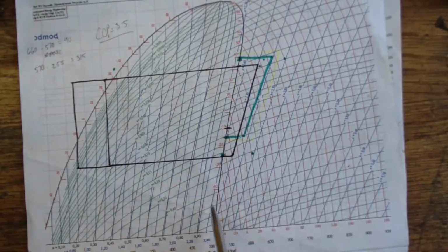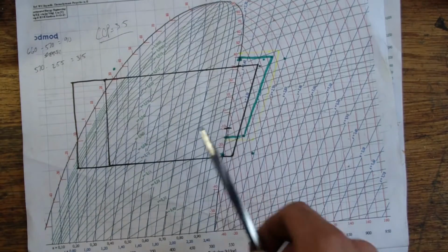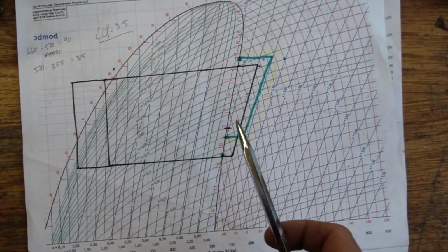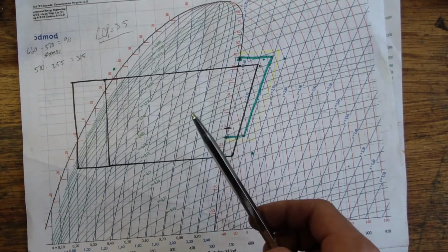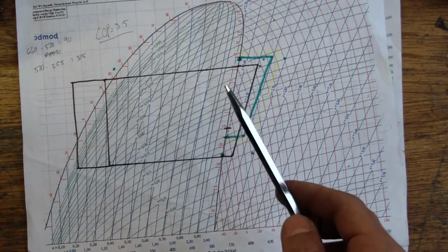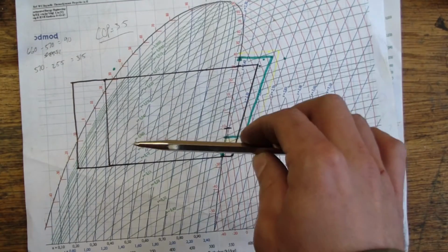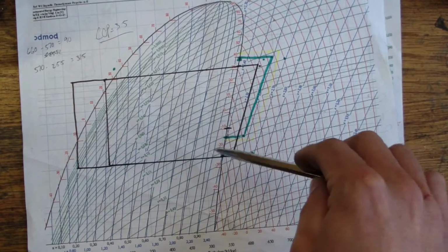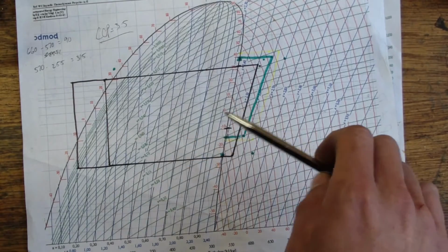So we can visualize here what effect the change in subcooling and the change in head pressure has. You can do a really simple theoretical COP calculation if you have an idea of what the pressures of your system are going to be, and you're looking to figure out the maximum possible COP for a perfect heat pump of that size. By simply dividing, I want to say, the absolute evaporator pressure. Now, this is assuming you're doing cooling work. The absolute evaporator pressure, that is not the gauge pressure, but the absolute pressure.